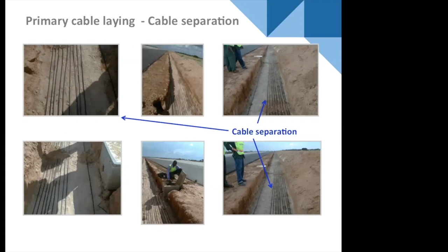Also, when we're installing cable, there is the criteria associated with bending allowance and also with tension. As you can imagine, if you've got a transformer pit alongside a runway, as shown here, and another transformer pit 60 meters down there, then the cable has got to go down there in a duct, along, and be pulled back up out of the next transformer pit. So the pulling tension is really important. Generically speaking, whatever the cross-sectional area of the current carrying conductor, so normally you use 6 millimeter square, that is 50 newtons per millimeter square. So for an AGL primary cable, that's 300 newtons we cannot exceed.